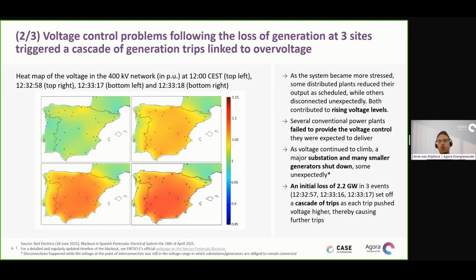So voltage control problems started happening after the loss of some sites. What seemed to have happened is that as the system became more stressed, there were some distributed plants, including renewables, that were reducing their output as scheduled by the dispatch, but some others disconnected unexpectedly. And both of these had the effect of contributing to rising voltage levels. On the next slide, I will explain why this was the case.